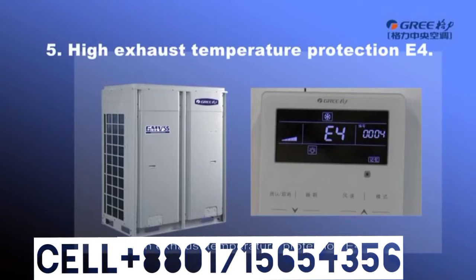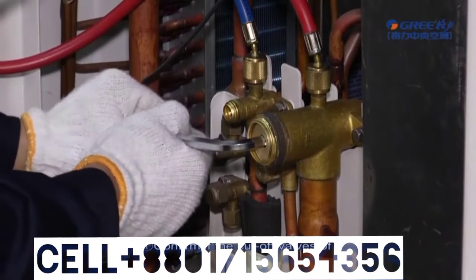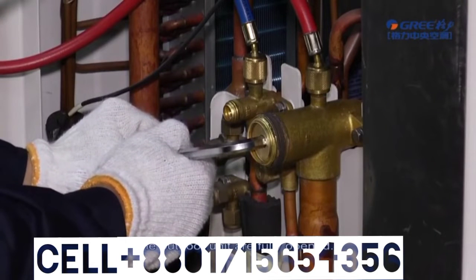5. High exhaust temperature protection, E4. E4 is mainly caused by insufficient suction volume of compressor and high pressure. Therefore, please check and solve the problem from the following aspects during maintenance. First, confirm if the cut-off valves of outdoor units are fully opened.